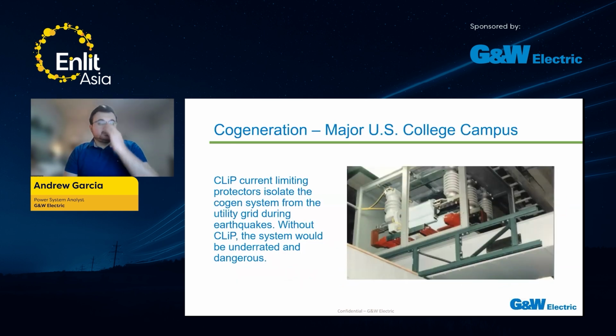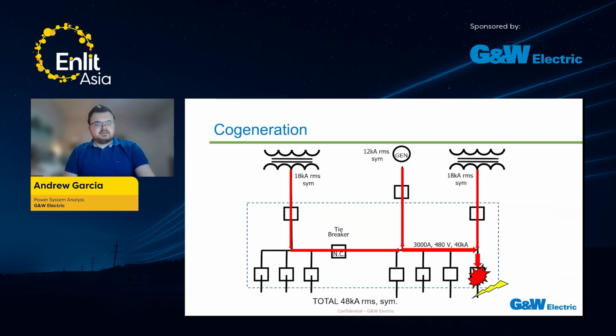Another example is cogeneration at a major US college campus, where current limiting protectors were used to isolate the cogeneration system from the utility grid during earthquakes. Without the CLiP, the system would be underrated and dangerous under these circumstances. There's an example of how this will work for cogen.